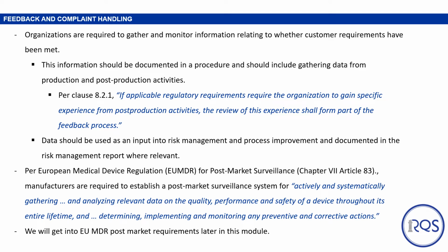Per European Union Medical Device Regulation, or EU MDR, for post-market surveillance, manufacturers are required to establish a post-market surveillance system for actively and systematically gathering and analyzing relevant data on quality, performance, and safety of a device throughout its entire lifetime, and determining, implementing, and monitoring any preventive and corrective actions. We will get into EU MDR post-market requirements later in this module.